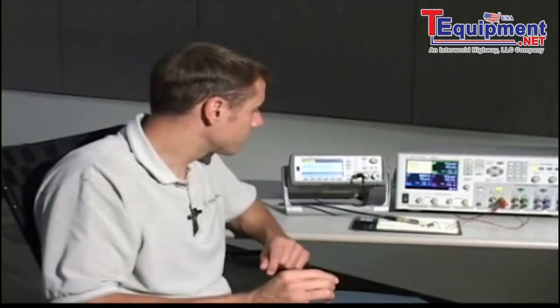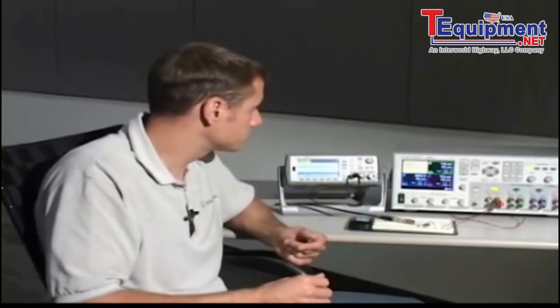Hi, today I'm going to talk to you about the math scaling feature on Agilent's 53200 series of universal counters. Now often when you're testing a time base or testing an oscillator or a clock, we're not concerned about the exact frequency display on the counter. We're more concerned about how far that reading is from some reference value, how many parts per million, how many percentage, things like that. So I'm going to show an example of the math scaling feature because it delivers that type of reading to you.